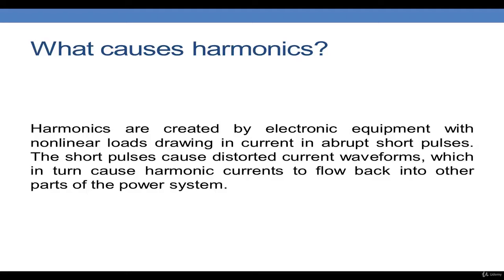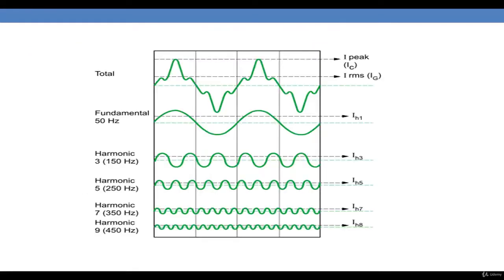Power electronic loads create distortions that superimpose on the fundamental frequency. Here we have the distorted current waveform, which can be resolved into several sine waves. The fundamental frequency is at 50 Hz. The third harmonic is three times the fundamental, which is 150 Hz, followed by the fifth and seventh harmonics. In power systems we are mostly concerned about the third, fifth, and seventh harmonics, and we neglect the ninth, eleventh, and so on, because their magnitudes are very small.